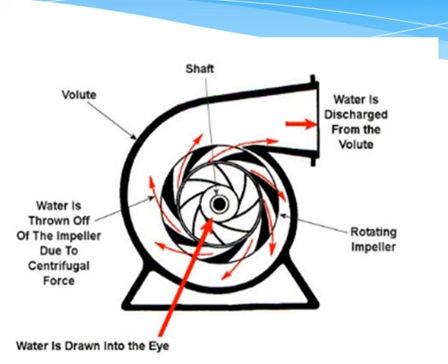And so that water then continues to travel in this circular direction here, you can see with my cursor. And as it continues to travel in this direction, you notice also that the diameter of this pump casing increases. This increasing diameter is what we refer to as the volute pump casing. So as our diameter increases, that area increases, we also end up with a decrease in velocity.